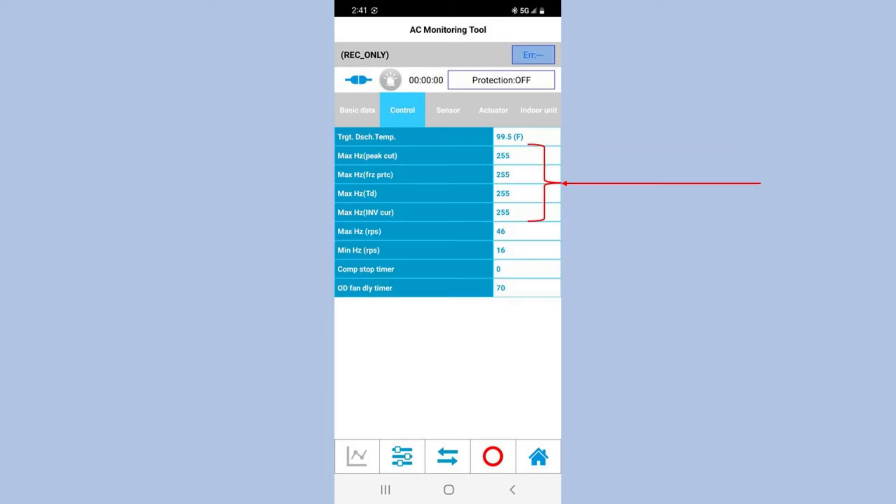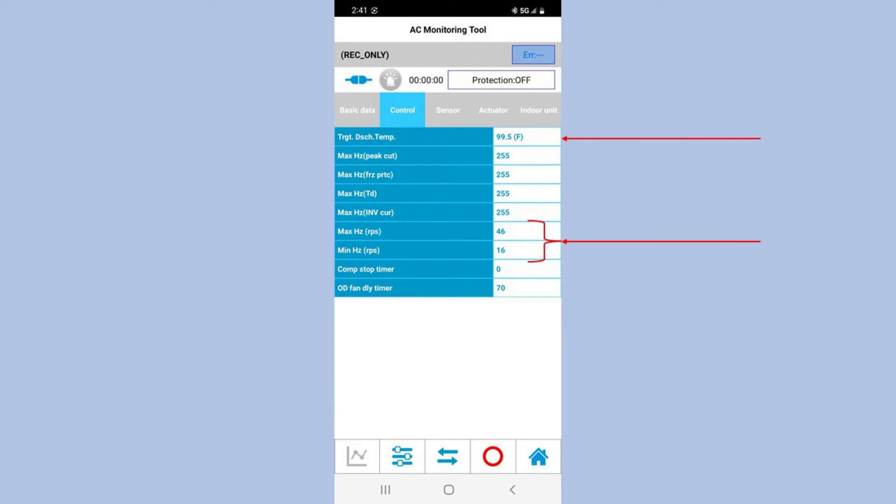Then we'll see these four items right here. These are the four items that are going to limit the frequency of the compressor and cause a protection mode. Again, that's not an error, it's designed to do that. So for example, if our coil on the indoor unit got down to 39 degrees, it'll go into protection mode, slowing the compressor down and showing your protection modes on. You still have at least 13 minutes from startup for the inverter frequency to go to full speed, but you'll see here the max is 46 at this time. It may increase or decrease and it might be limited by one of the protection modes.